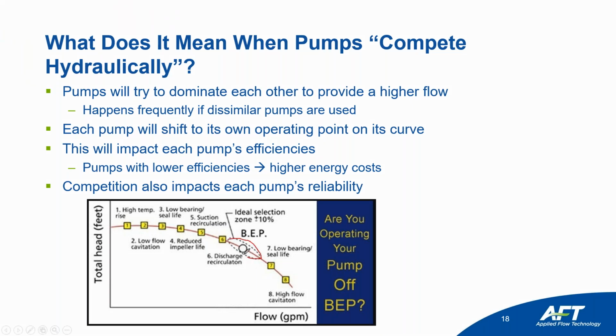So this is the sweet spot where you want to operate. That is your design point. Your best efficiency point is right here, where you have the highest efficiency. You want to try and be within 10 to 20% of that area. As you ride back on your curve, when your flow decreases, you start to encounter all these different problems: high temperature rise, low flow cavitation, low bearing and seal life due to vibrations, reduced impeller life, suction recirculation, discharge recirculation. Those are all bad things that you want to avoid, and it happens when you're operating at flow rates less than your best efficiency point. When you get higher than your BEP, you also have issues with seals and then high flow cavitation. So definitely stuff that you want to avoid there.